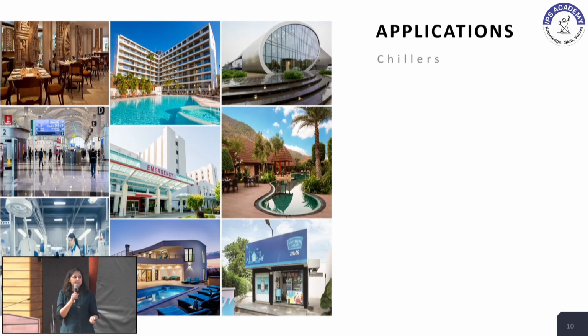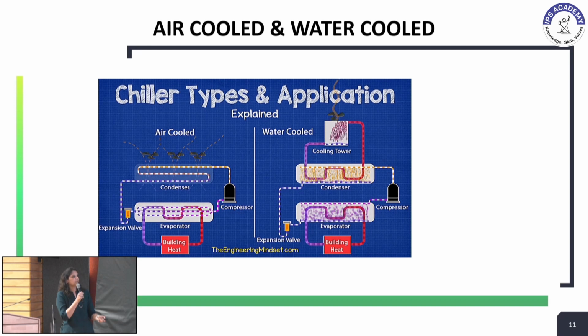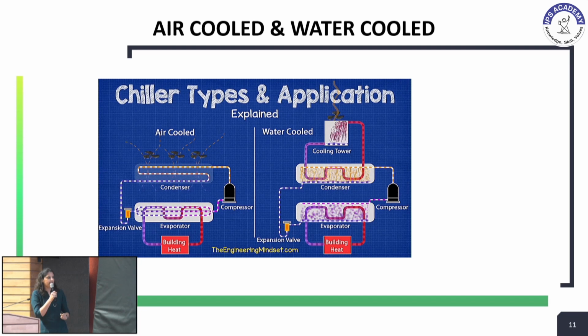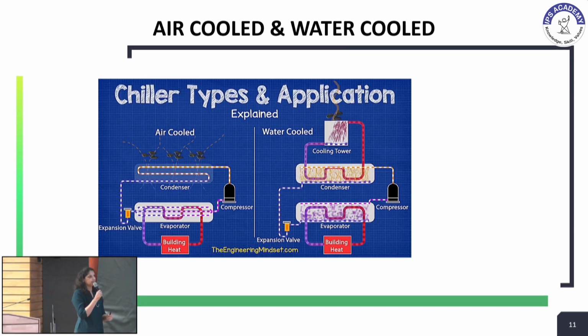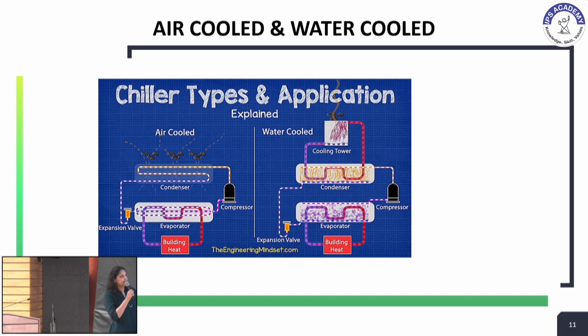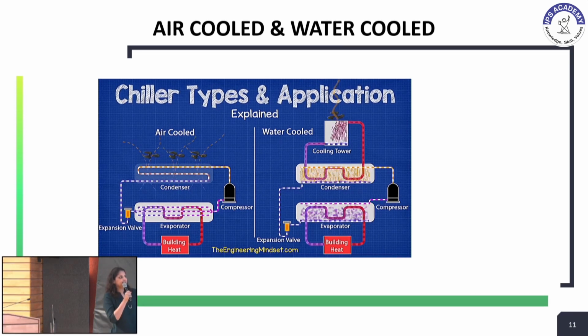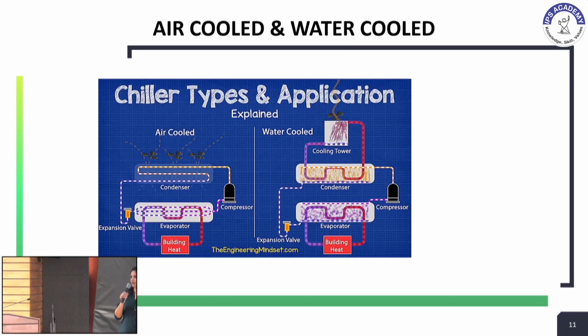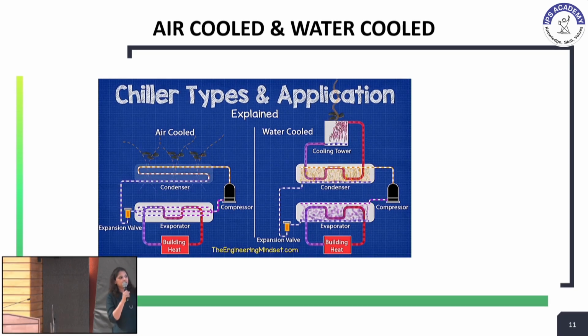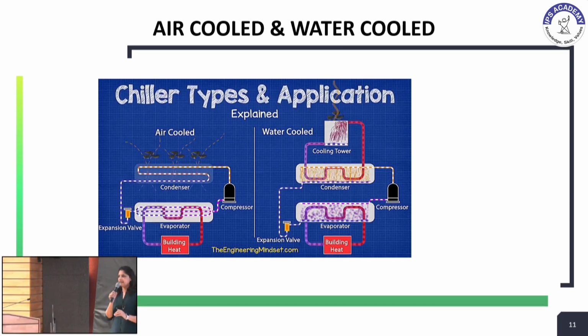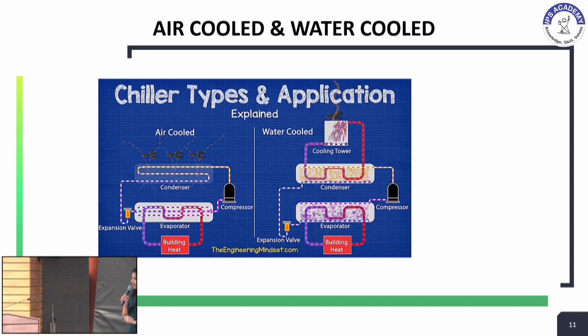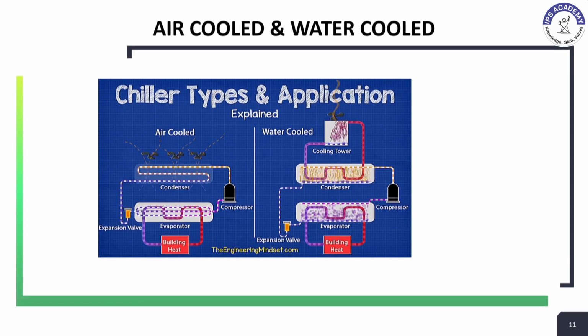So we come to applications now. Chillers can be defined into broadly 2 parts. One is an air-cooled chiller, and second is the water-cooled chiller. You see, in air-cooled chiller, the heat is getting dissipated out of the chiller to the environment. However, in a water-cooled chiller, the heat dissipation has to occur via a cooling tower. So, water-cooled chillers are slightly more complex chillers which are applied in specific applications.